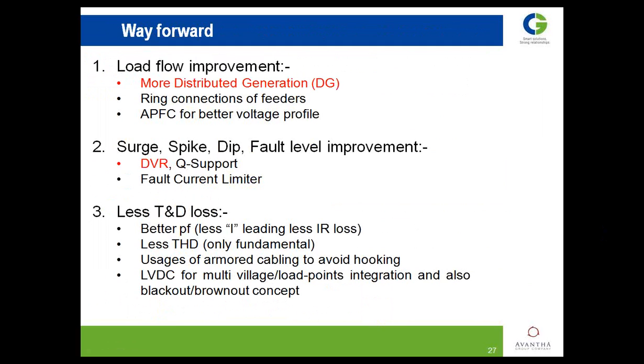And more than that, this Q improvement which Pannalal tries to cover, and that harmonic improvement which gives unnecessary fifth harmonic, second harmonic, which creates nothing for the system, because all that torque and all sorts of things depend on the fundamental one. So how can I eliminate those unnecessary harmonics except the fundamental, and how can I also reduce the Q part, make more P and reduce the I, and create an impact on my IR losses of the system?